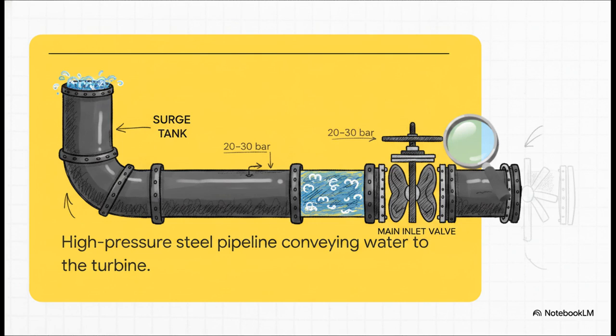Safely past the surge tank, the water takes a steep drop into the penstock. This is a high-pressure welded steel pipeline that conveys the water directly to the turbine. Because of the unbelievable weight of all that water stacked up above it, it has to be designed to withstand up to 20 to 30 bar of pressure, depending on the specific site. And right at the very end, it's isolated by the main inlet valve, usually this massive butterfly valve that controls the water flow to the turbine.